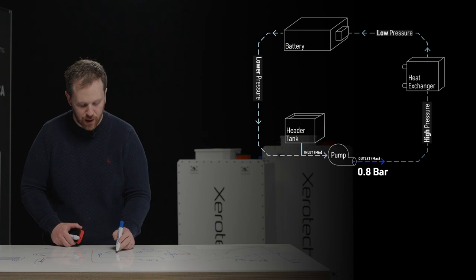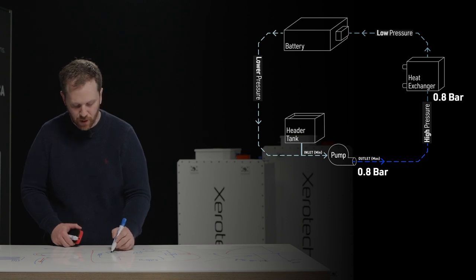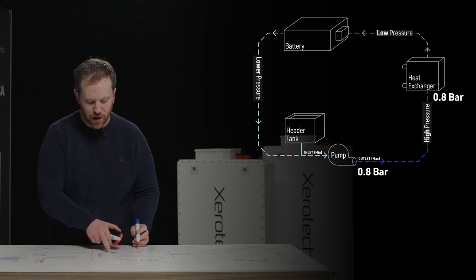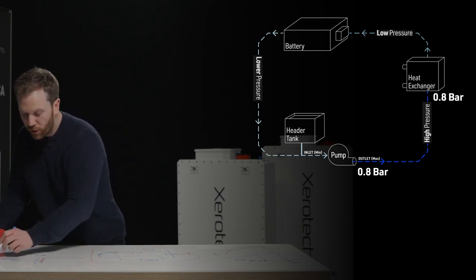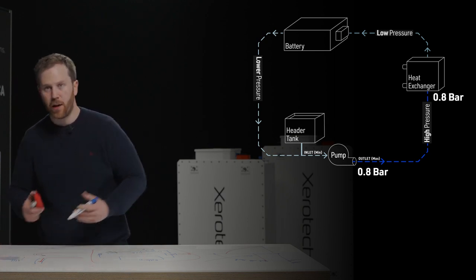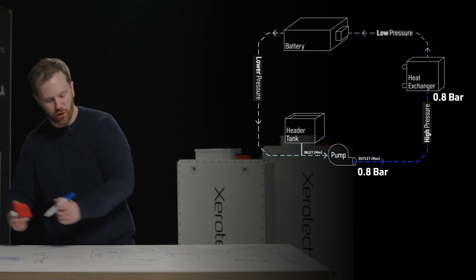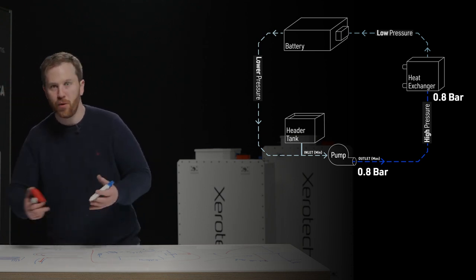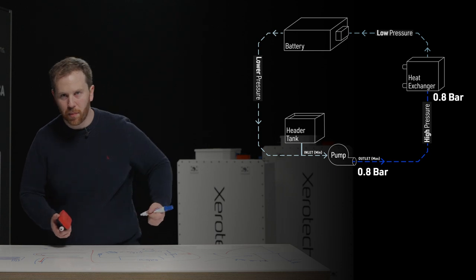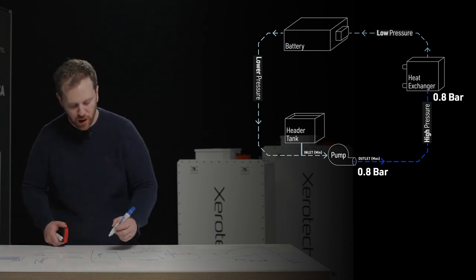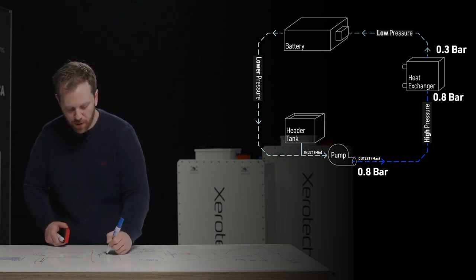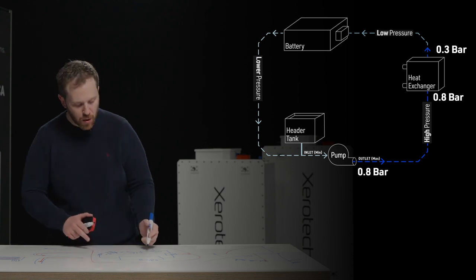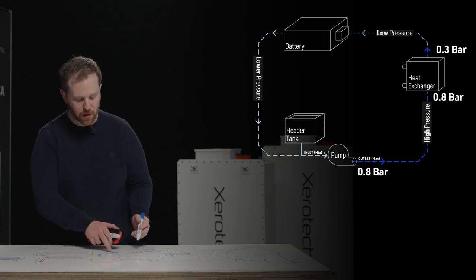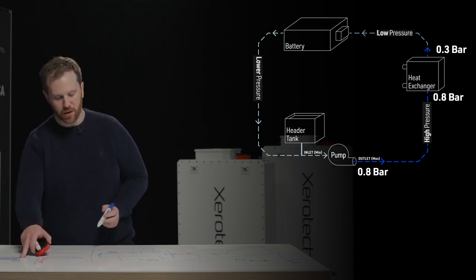So on the inlet side of the heat exchanger, we see roughly 0.8 bar here. As it passes through the heat exchanger, the water goes through this convoluted path. It loses energy because it's being pushed through that, so you get a pressure drop. You're losing pressure on the system. The pump is having to pump it through and loses energy. So the pressure coming out might be 0.3 bar. So most of the energy of the pump is expended getting through the plate heat exchanger.